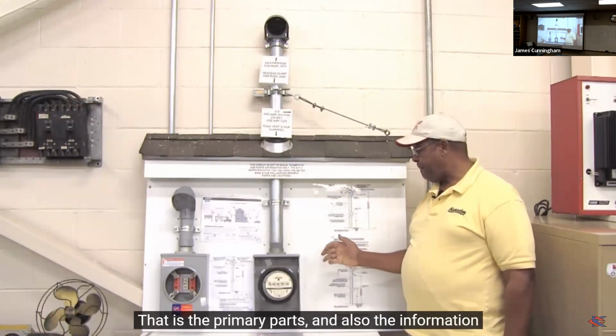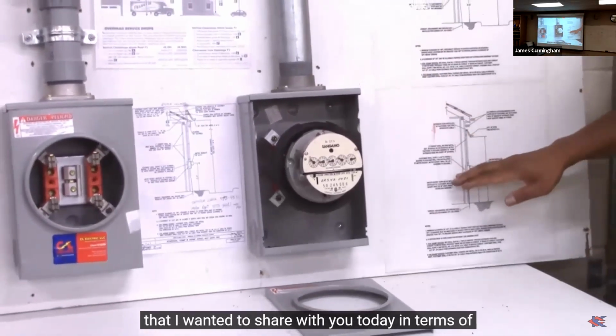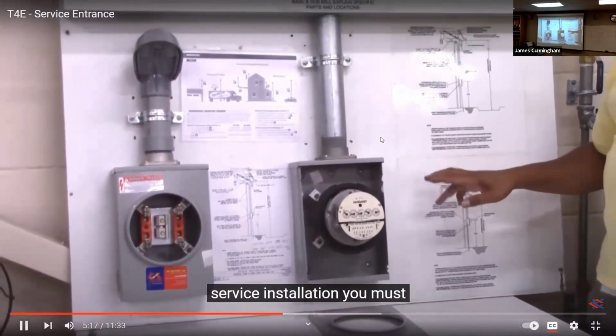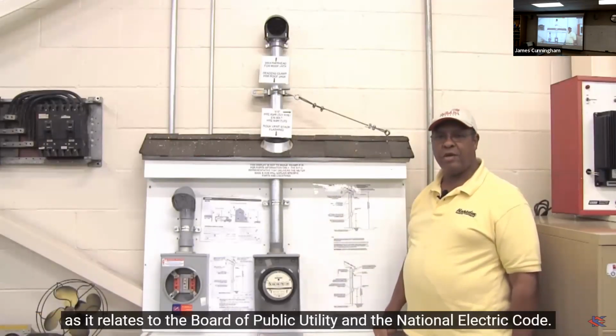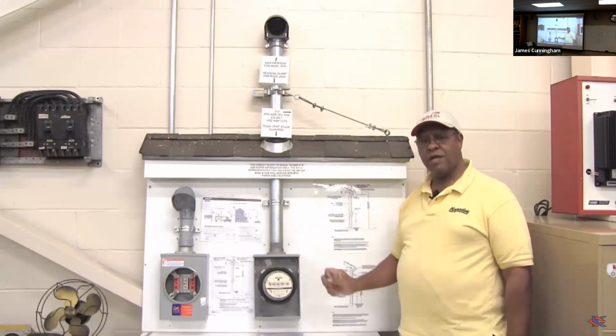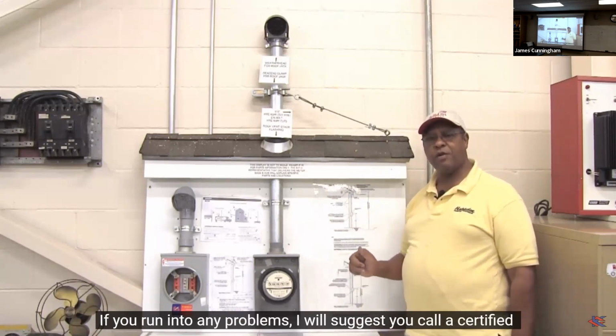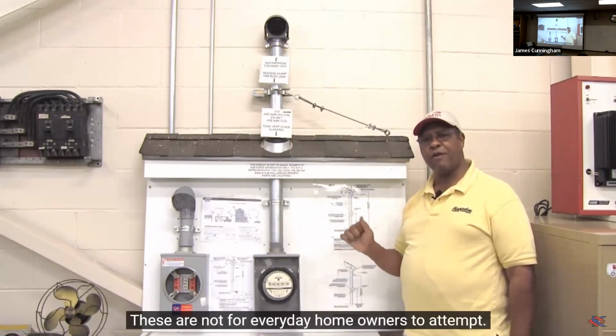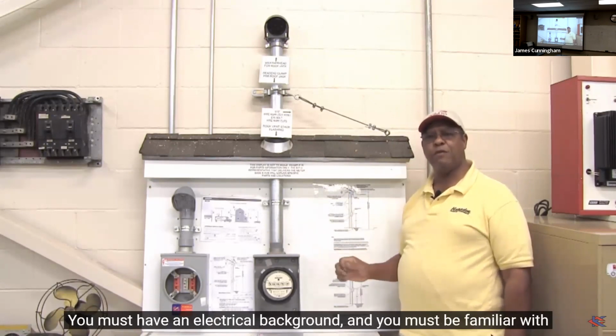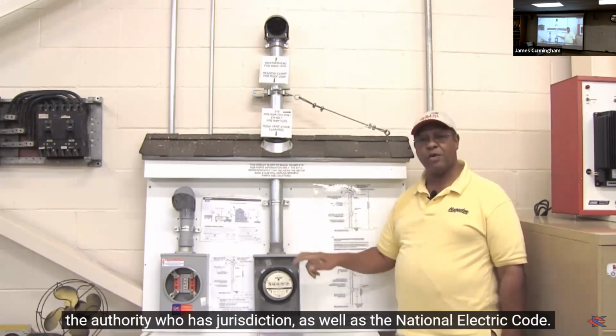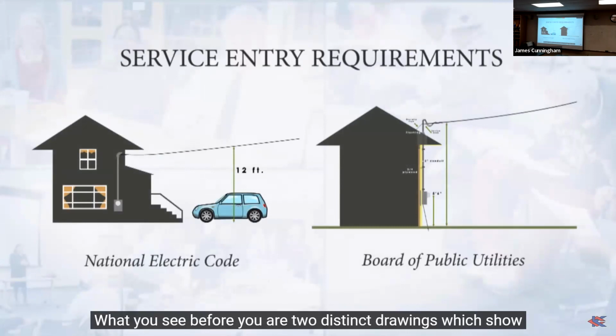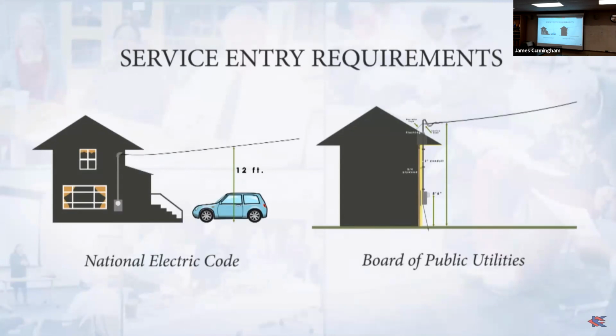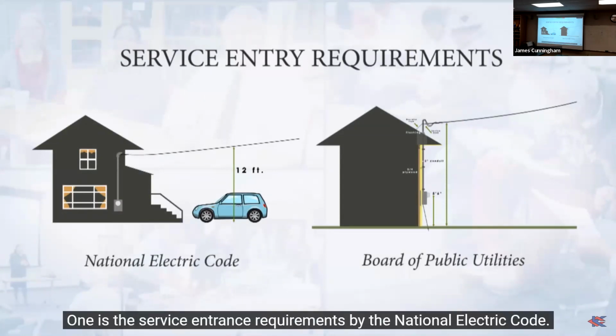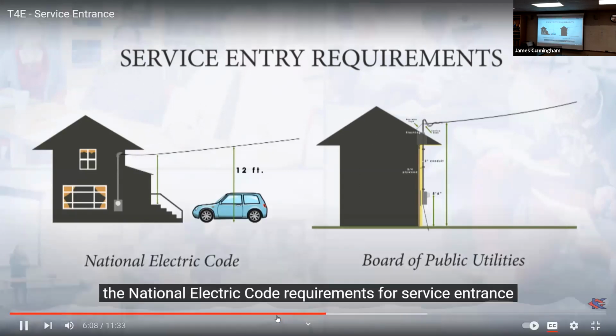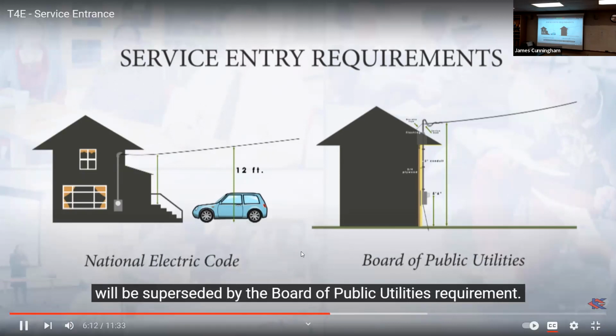That is the primary parts and also the information that I wanted to share with you today. Whenever you're going to do a service installation, you must have all of these specifications as it relates to the Board of Public Utilities and the National Electric Code. If you run into any problems, I would suggest you call a certified or qualified electrician in order to help you. These are not for everyday homeowners to attempt. You must have an electrical background and you must be familiar with the authority who has jurisdiction as well as the National Electric Code. What you see before you are two distinct drawings which show the service entrance requirements. One is the service entrance requirements by the National Electric Code and the service entrance requirements for the Board of Public Utilities. And since we're in Wyandotte County, the National Electric Code requirements for service entrance will be superseded by the Board of Public Utilities requirement.